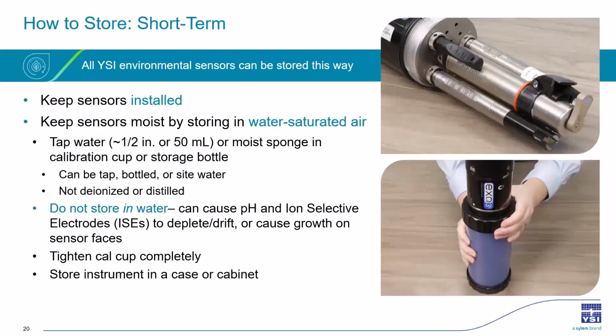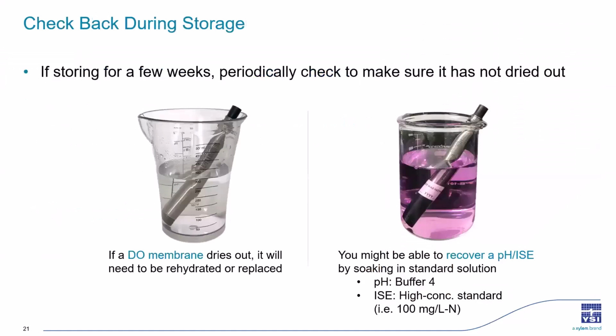You're also going to want to make sure the calibration cup or storage bottle is fully sealed on the sensors to prevent them from drying out at all. And then you can go ahead and store your instrument in a case for transportation or in a cabinet to protect it if you're not using it right away. If you're storing your sensors for closer to 4 weeks, so the longer side of the short-term storage, you should check on them periodically, just a couple times, just to make sure they're not drying out.